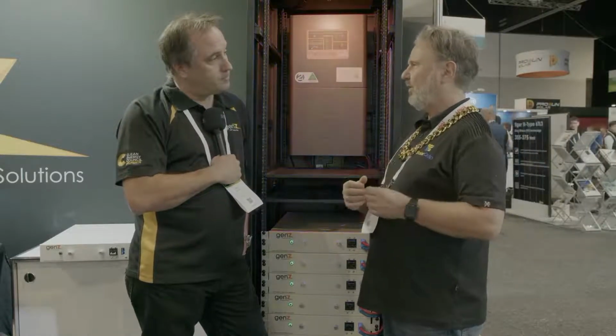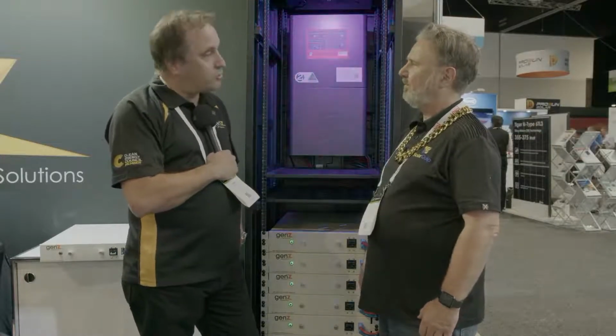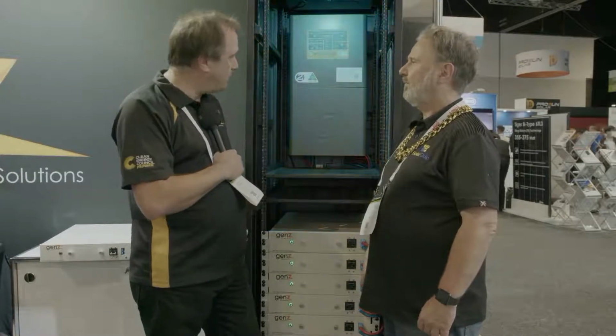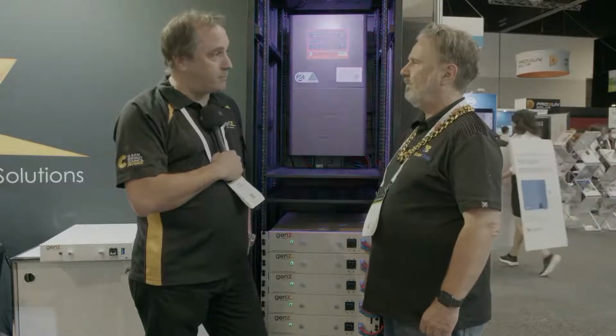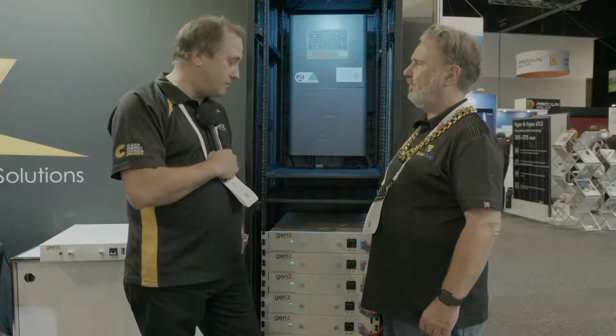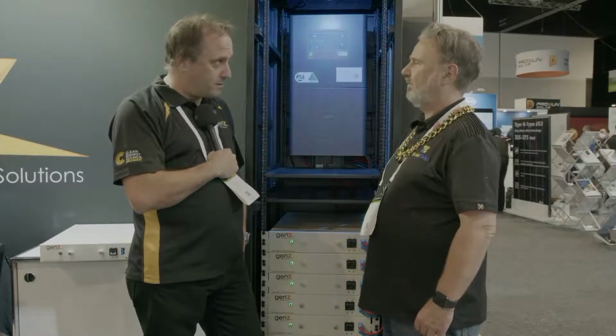Now do they work with one particular inverter, like Selectronic, or can you work with others? No, that's the beauty. They all have internal BMSs, so they actually work with any inverter that's out there. Traditionally we recommend Cellectronics because they have a drop-down menu where you see the 3 kilowatt or 2 kilowatt battery, you put in the number of batteries and basically about 3 or 4 settings, and you're good to go. It's already preset with our set points.